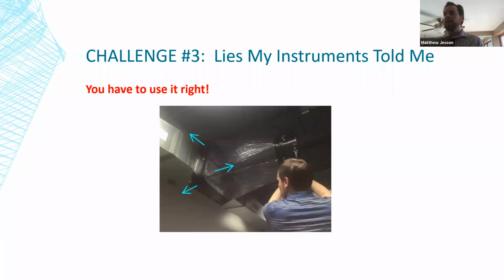So in this case, can you put a hood up to a grill like this and get a reading? You sure can, but is it going to be correct? If you can see in this clear hood, the top and bottom of the hood are not sealed off to the duct or anything else. So it's just open to the air there. Air can flow in and out of there as it pleases.